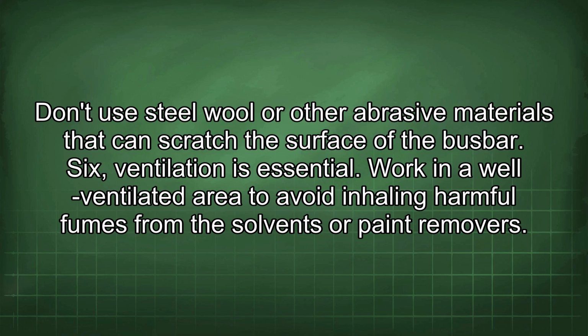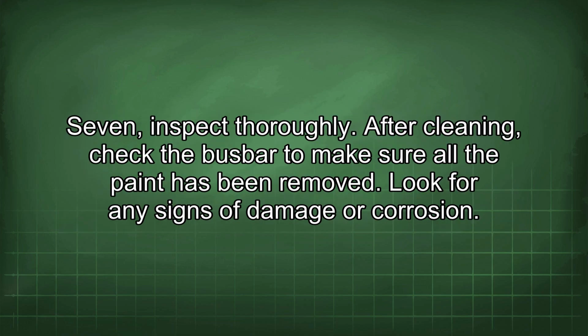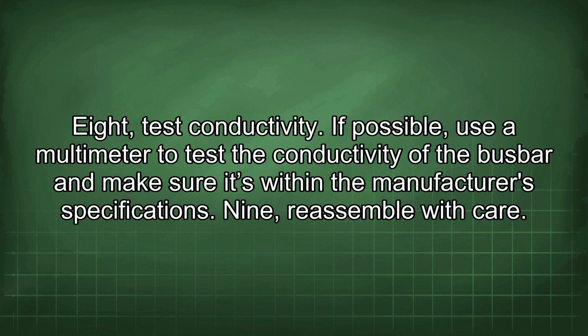6. Ventilation is essential. Work in a well-ventilated area to avoid inhaling harmful fumes from the solvents or paint removers. 7. Inspect thoroughly. After cleaning, check the busbar to make sure all the paint has been removed. Look for any signs of damage or corrosion. 8. Test conductivity. If possible, use a multimeter to test the conductivity of the busbar and make sure it's within the manufacturer's specifications. 9. Reassemble with care.